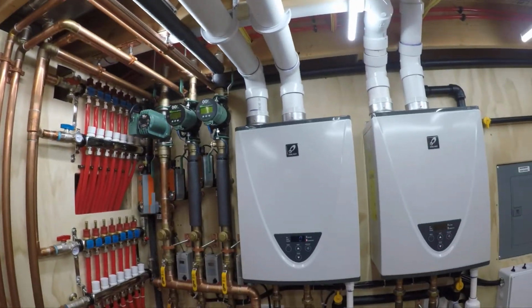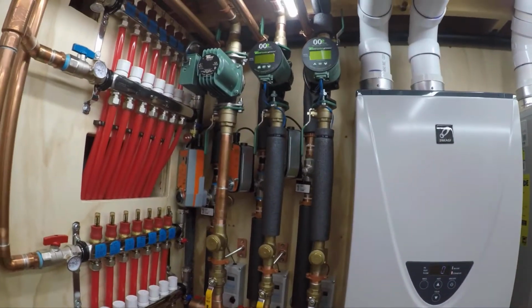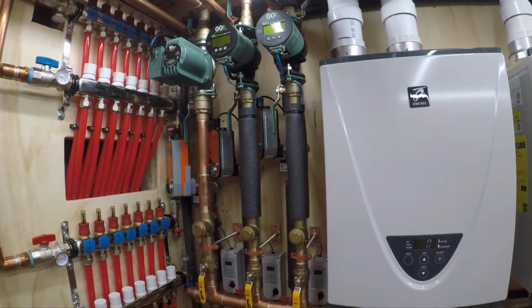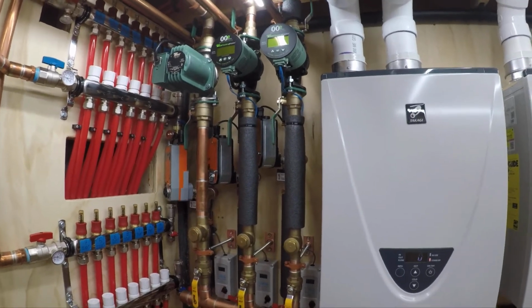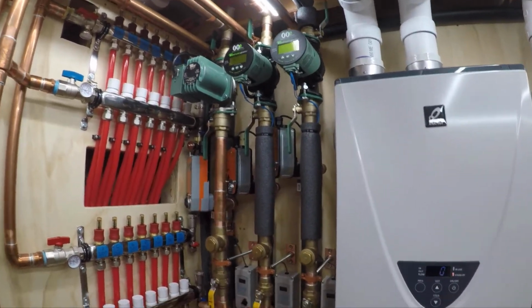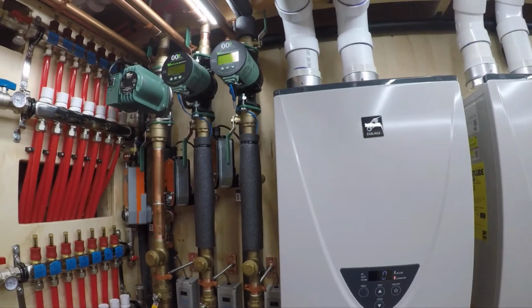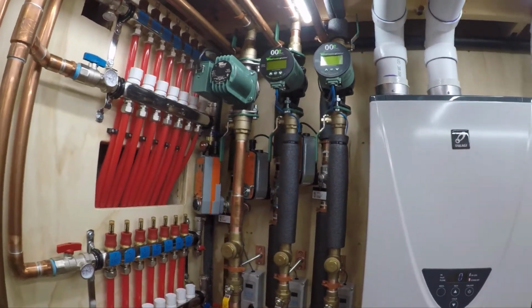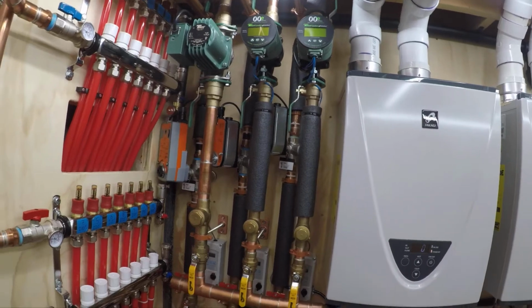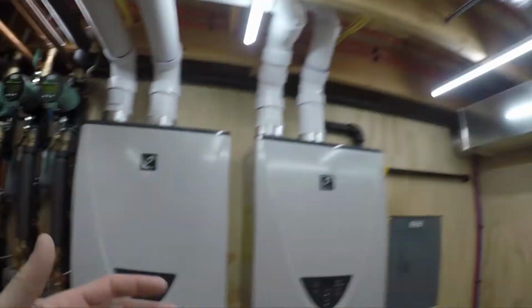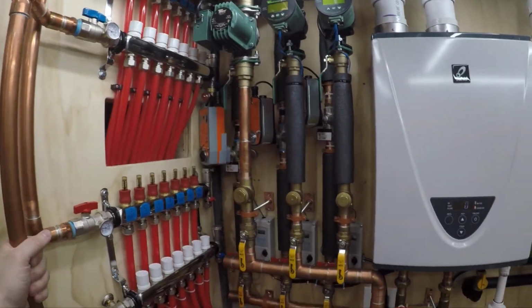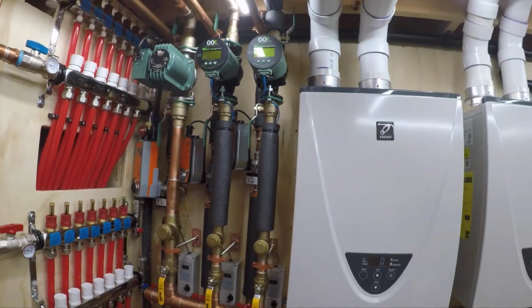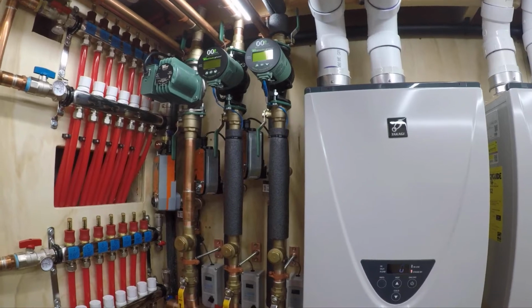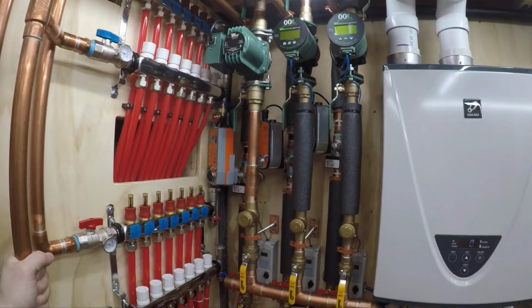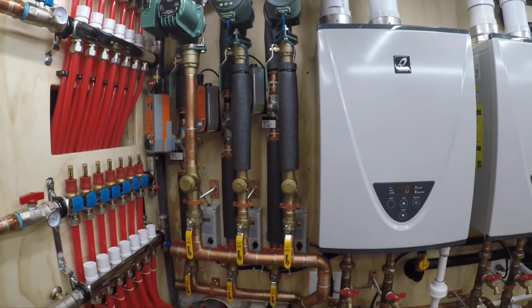Well, I think thermostats would compete with my furnace, with my forced air, because the air right now in my bedrooms up there is 68, 69, 70 degrees. So unless I'm turning them way up to get the floors warm, a thermostat, unless I put a slab or a floor sensor in, which Tecmar and them do make, but I don't have any of those. Unless I do all of that, really, the thermostats are going to be fighting with my forced air furnace.